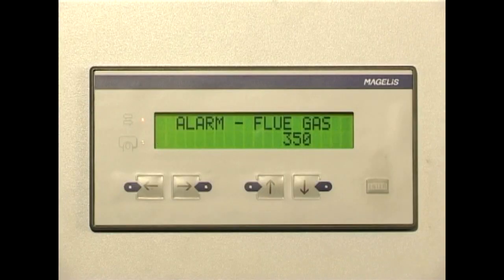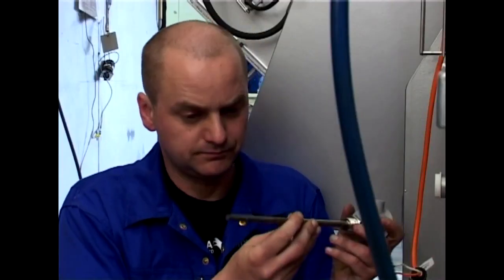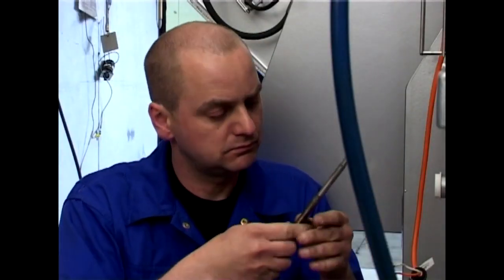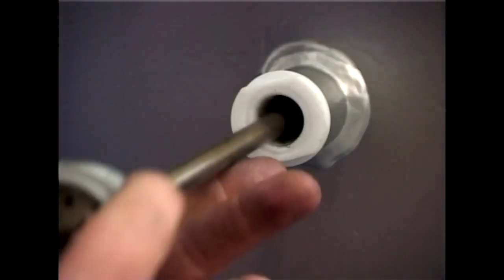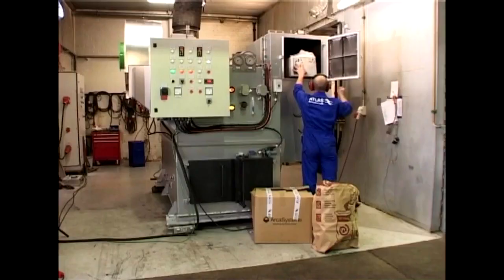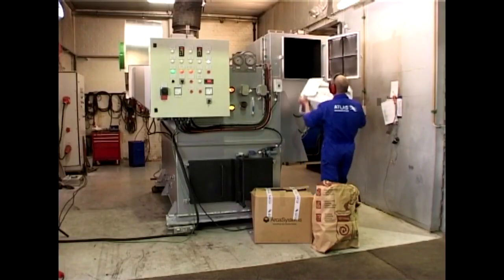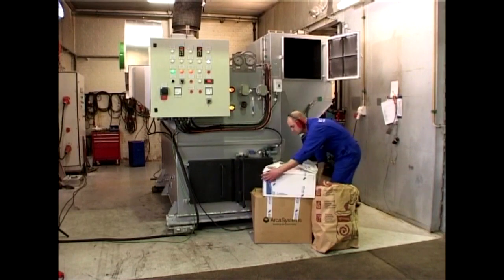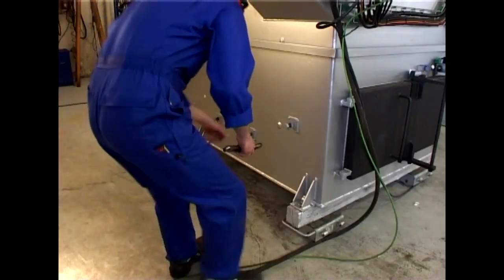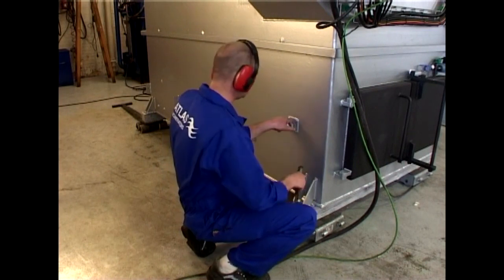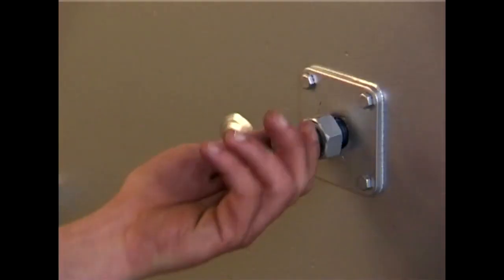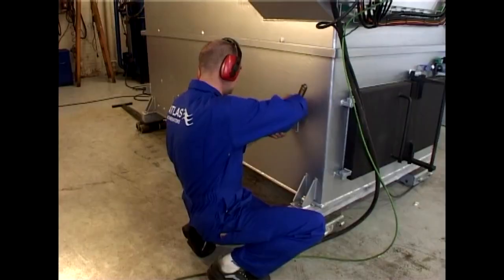This alarm comes when the temperature in the funnel system is higher than expected. A frequent reason for this alarm is that the thermocouple in the funnel is faulty. To fix this, find and replace the faulty thermocouple. Another reason can be that the calorific value of the waste is too high. The way to solve this is by reducing the loading of waste into the incinerator. Finally, a different approach to overcoming this problem is to add more cooling air to the flue gases. This can be done by opening the air nozzles in the secondary chamber.